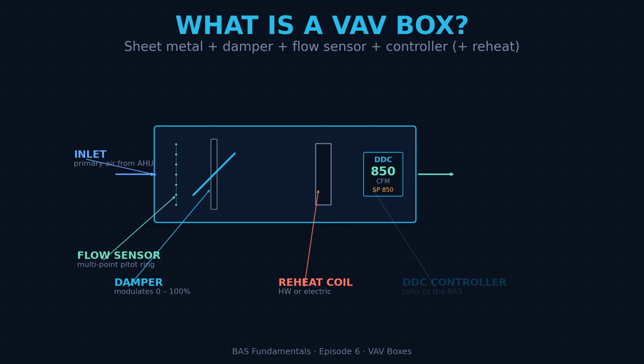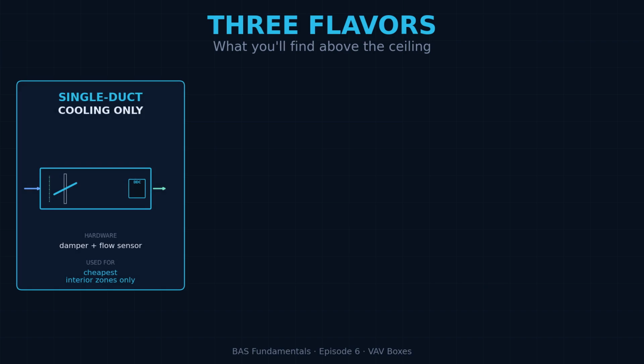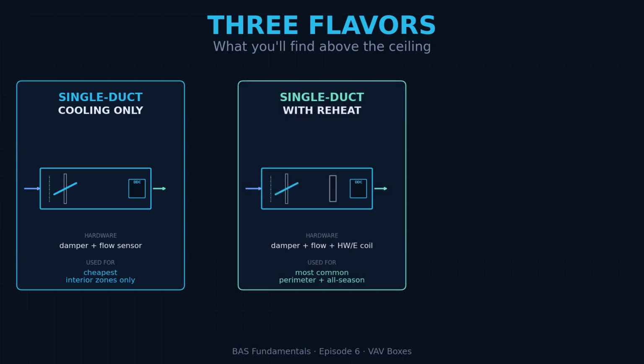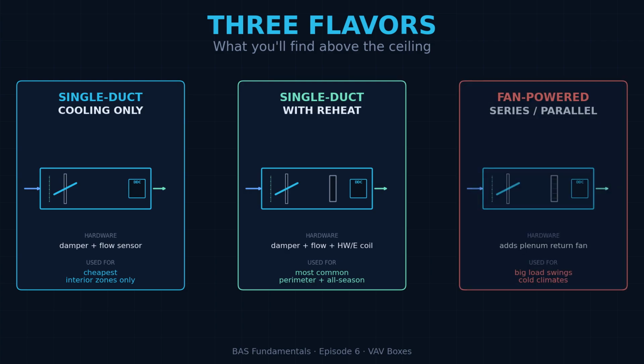The AHU sends cold air down the main duct. The VAV box decides how much of that cold air actually gets into your office. There are three common flavors you'll see in the field. Single duct, cooling only, just a damper and a flow sensor, cheapest, used where you never need heat. Single duct with reheat, adds a coil so the box can warm the air back up for heating season or perimeter zones. And fan-powered boxes, which come in two styles, series and parallel. Fan-powered boxes pull return air from the ceiling plenum and mix it with primary cold air. More hardware, more cost, but they handle big load swings and cold climates better.